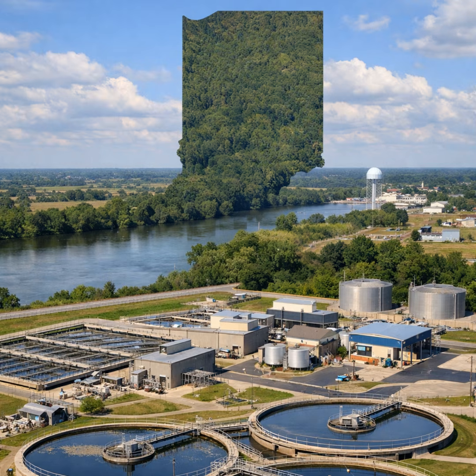And filamentous bacteria thrive in low DO and low food to microorganism environments. So where the DO, dissolved oxygen, is very low, and the food to microorganisms ratio is low, that means there's not a lot of influent wastewater coming in, and not a lot of food to feed the microorganisms, the biomass. That's where filamentous organisms thrive and grow.